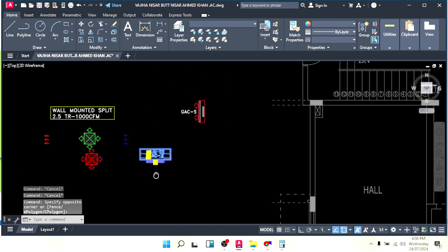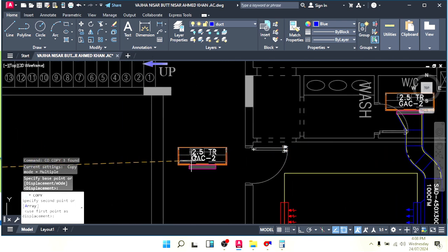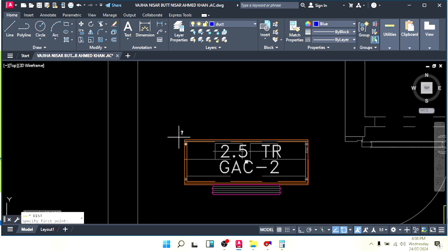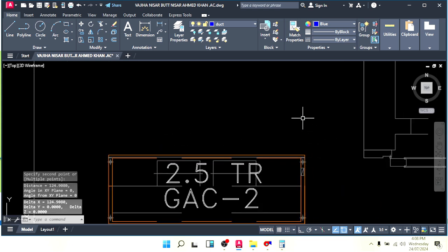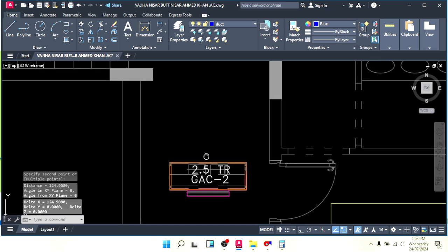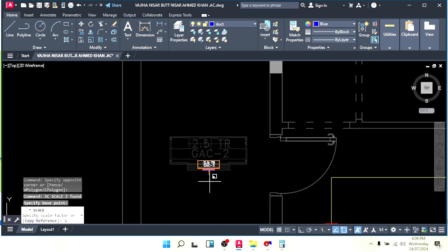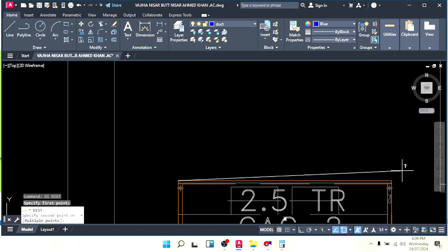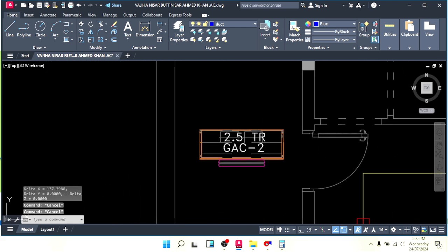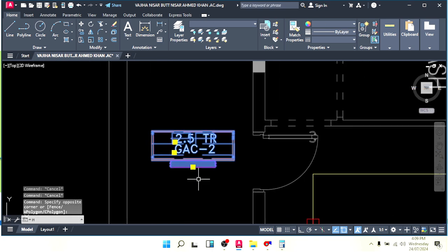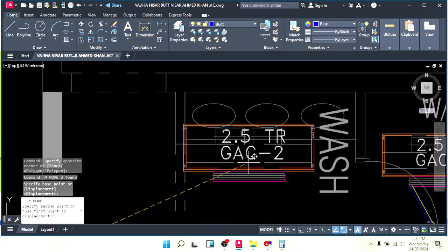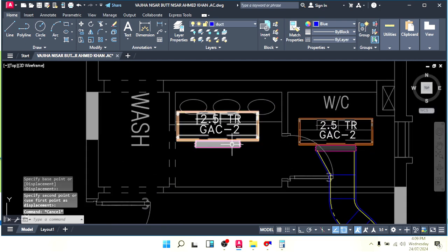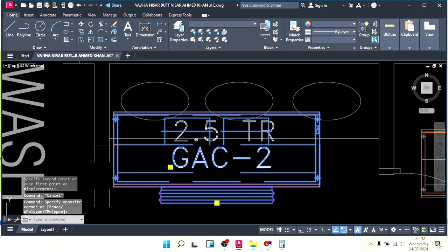Okay, so let's take the machine. 3-ton machine length approximate 130 or 140 centimeter the width. Now here we have 124, it's nearby, even we can make a little bigger, 1.1. This is 137. Yeah, this is acceptable. The size of the machine depends on the units, what the unit he wants. Here he wants Mitsubishi, so I know the Mitsubishi approximate sizes, so I'm following that one.